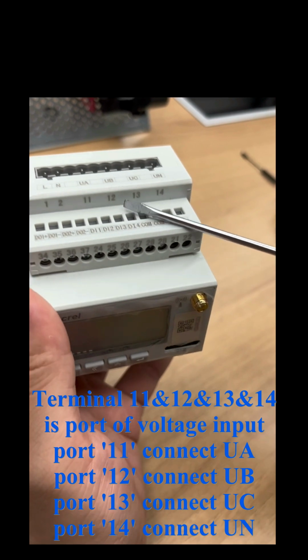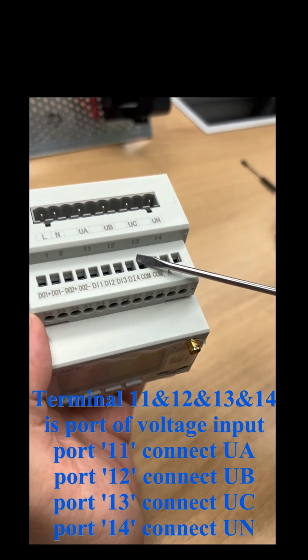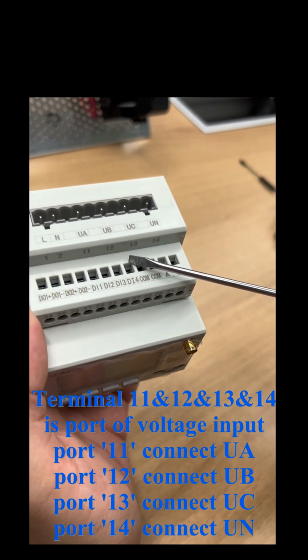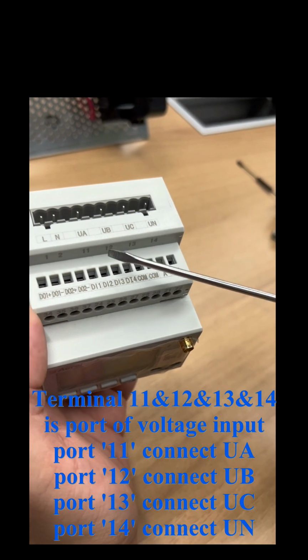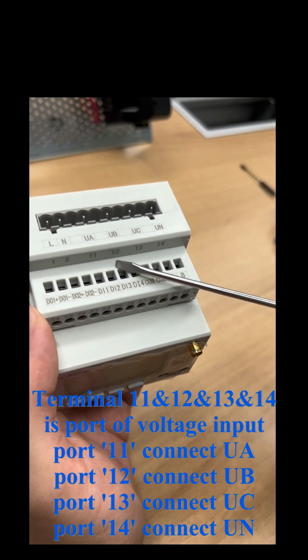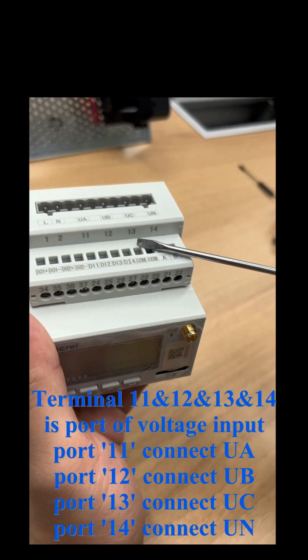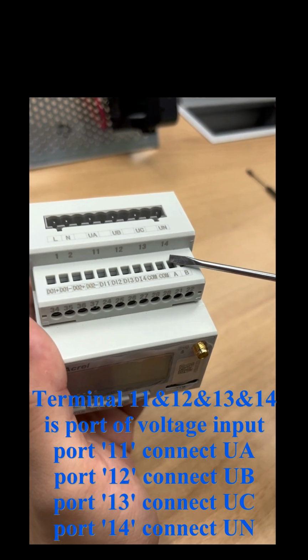Terminals 11, 12, 13, and 14 are the voltage input ports. Port 11 connects to UA, port 12 connects to UB, port 13 connects to UC, and port 14 connects to UN.